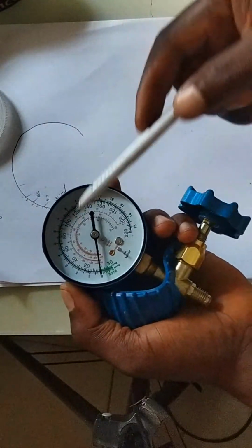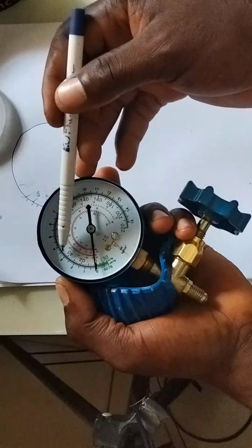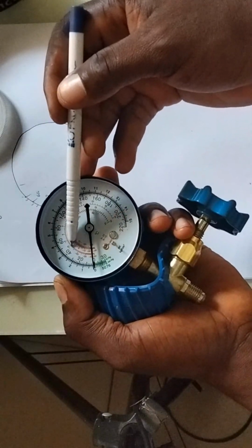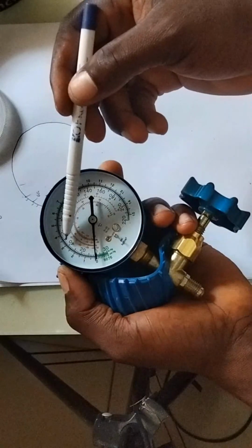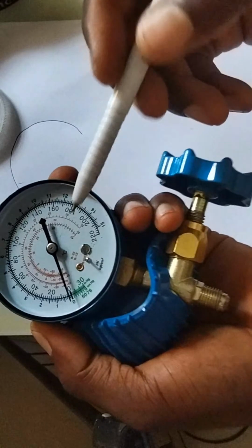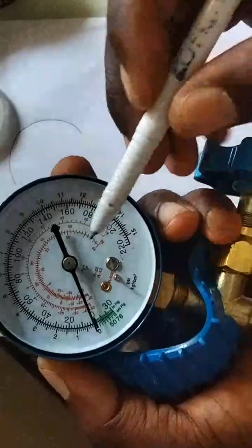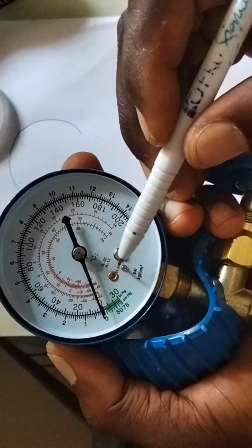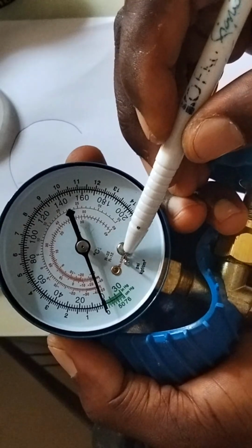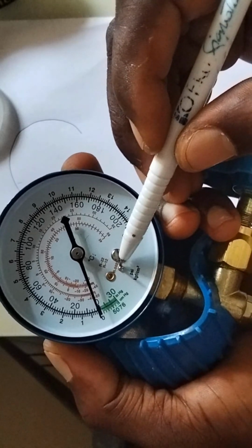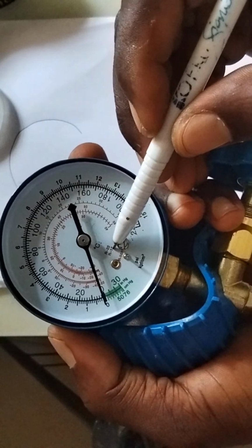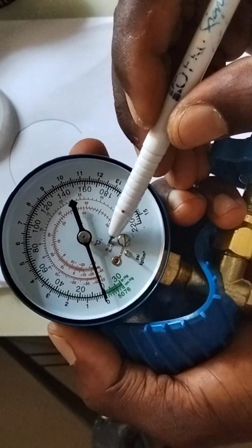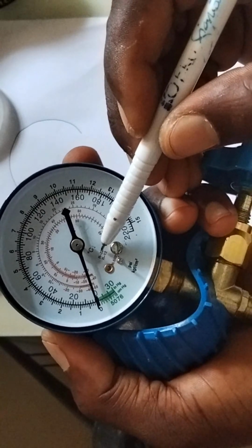This is a single gauge. As I say, this is a single gauge. If you observe on the single gauge, you have curve 1, curve 2, and also another curve. Look closely again, because you need to understand the readings for the different refrigerants involved here. We have R502 here. We also have R12 here, and we also have R22 here. Understand?